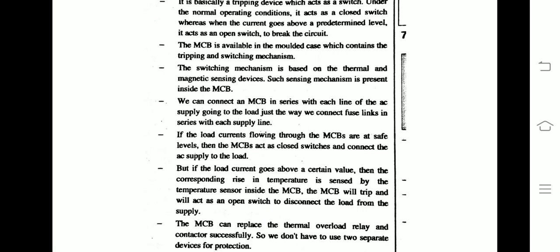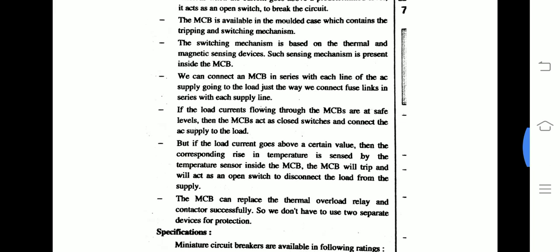The switching mechanism inside the MCB is based on thermal and magnetic sensing devices. We can connect an MCB in series with each line of the AC supply going to the load, just the way we connect fuse links in series with each supply line.